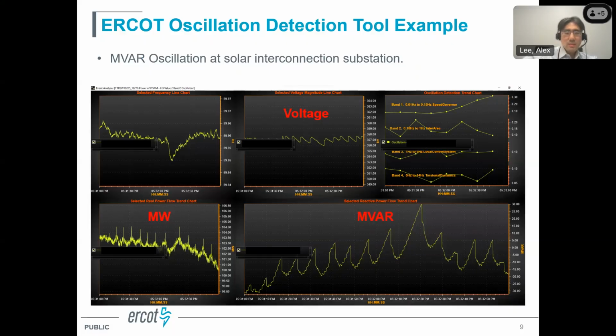This example is a megavar oscillation at a solar PV plant interconnected at a nearby substation. The lower right shows the megavar reactive power, with up to 30-40 megavar of oscillations, which reflects voltage oscillations in the middle upper panes. Another thing to note is that this oscillation did not happen during low megawatt output, meaning close to 0 megawatt. The lower left pane shows a little over 100 megawatt of injection from the solar plant.